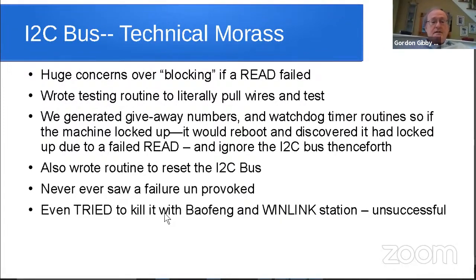Okay, so we ran into big problems with the I2C bus. There was a big concern that this could block if a read failed, and everybody was concerned that this could happen. And if it happened, then the ventilator would come to a screeching halt because it was a stop for the entire code. So I wrote a testing routine where we would literally pull wires and see if the ventilator would die. Ashhar came up with a solution for this with a watchdog timer routine where we generated giveaway numbers. And if those numbers disappeared, then we knew the machine had died and had been rebooted by the watchdog timer. And then we would know that the I2C bus had failed, and we would ignore it thenceforth, and we would move forward with hard-coded numbers. Sort of like if your computer in your car dies, it goes to hard-coded numbers for how to set things.